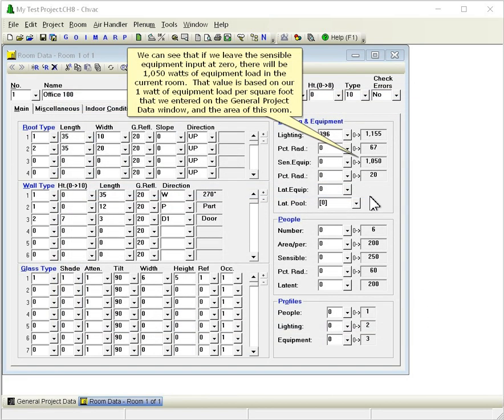If we leave the sensible equipment input at zero, there will be 1050 watts of equipment load in the current room. That value is based on our 1 watt of equipment load per square foot that we entered on the general project data window and the area of this room.